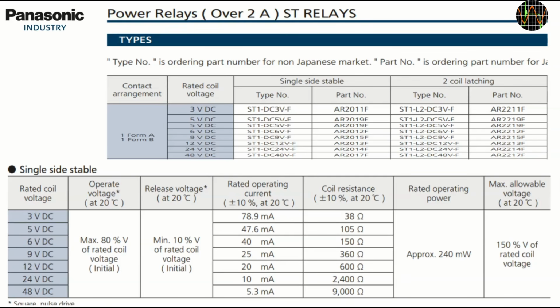Curiosity got the better of me and I downloaded the datasheet of the relays. These are from Panasonic. Of interest is the 12 volt version used in the earth resistance circuit and the 48 volt version which are used in the insulation resistance section. In either case, the part number indicates a single side stable version. It takes a maximum of 80% of the rated coil voltage to operate the relay. In our case, that would be 9.6 volts, but that is the maximum. It might operate well before that.